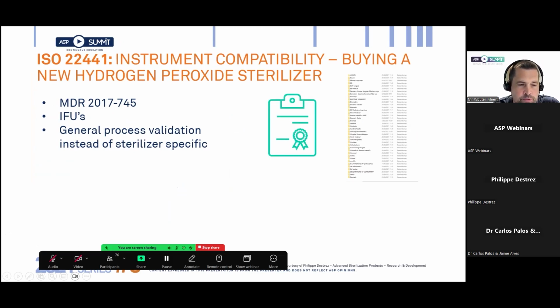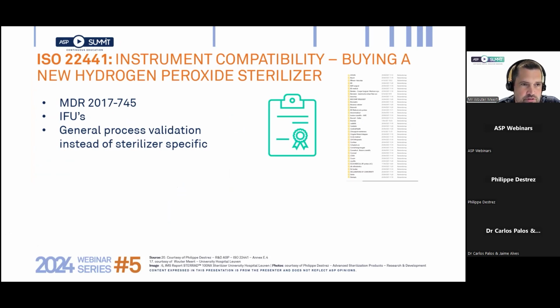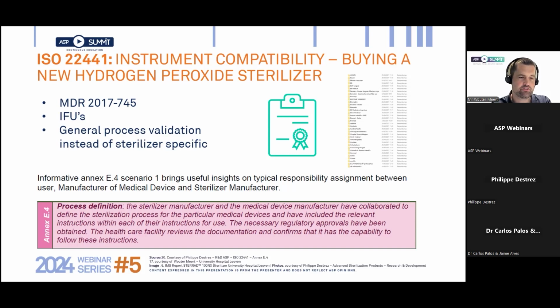It's certainly the IFU, because if we look at the European guidelines now with the new medical device regulation, it's really strict that medical device manufacturers need to make sure that in their validation of their reprocessing cycles, they look at which sterilization principle can be used to safely reprocess their instruments and to make sure their life cycle is as normal as generally possible. That means you look at the instructions for use, and hopefully there is a general idea about which process can be used. And I hope with the new norm that instead of every manufacturer validating every type of hydrogen peroxide sterilizer, it will be a more general thing that's tested.